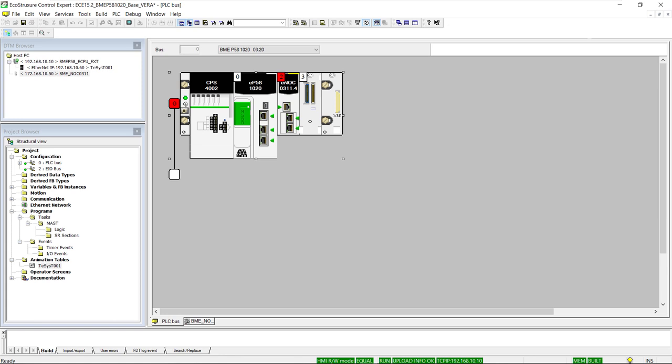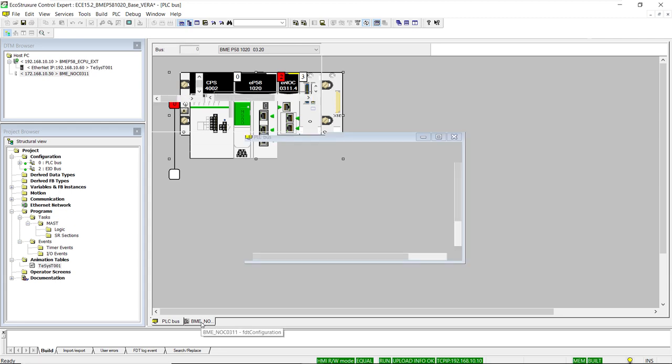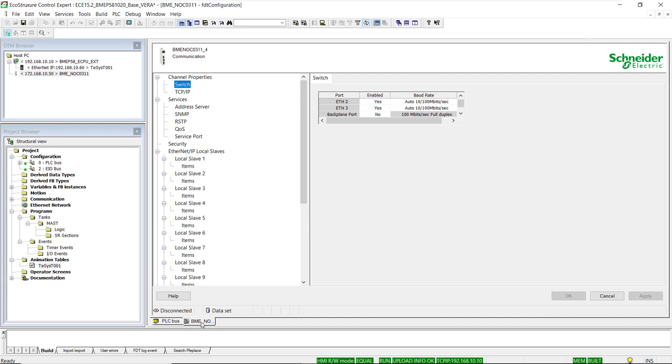This could also help improve asset management in the control system. The CPU and NOC modules in the M580 controller have the same type of object dictionary, which could be extremely useful to remotely access identity information of the processor or other modules on the PLC backplane not directly connected to the supervision network. In the sample project, the NOC module is connected to the external SCADA system, but its connection to the Ethernet bus on the backplane is disabled.